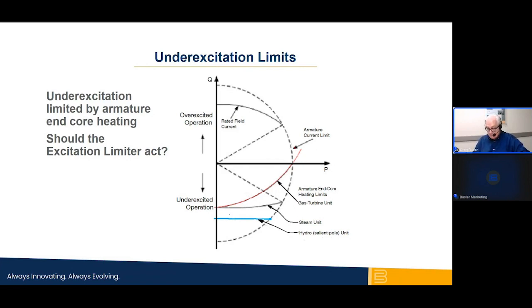There are conditions associated with underexcited synchronous machines that bear examination when establishing the underexcitation limiter. The capability curve for the machine includes a steady state stability curve, SSL. The trace of that SSL curve will most commonly intersect the power, P, axis. You see in our diagram here, we have two axes, P and Q. The trace of the SSL curve will most commonly intersect the power P axis of the graph at the point where the apparent power limit circle also intersects. You see there the orange arc.